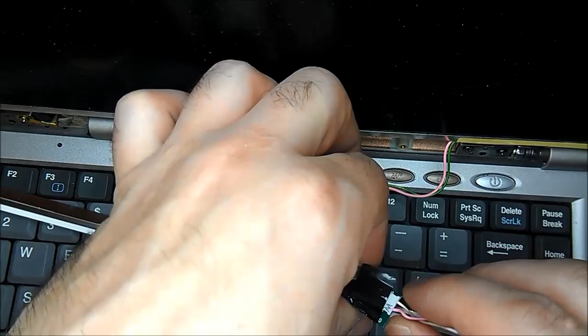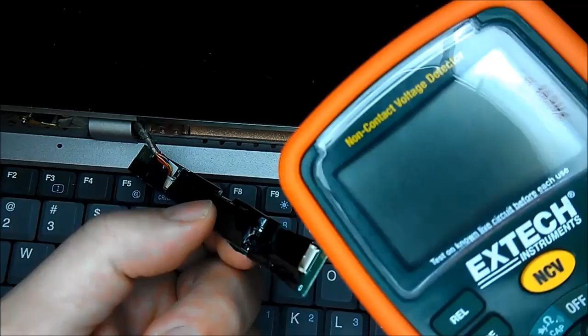Now, if you're tempted to check voltages, never check voltages on this side of the board. It doesn't matter what kind of meter you have. If it's one of these, they usually go up to 600 volts, or even one of these good ones, you'd need a very high-end meter over 1,000 volts. Usually the ones we carry go up to 600 volts. So you don't want to touch or probe that end to measure voltages, since it can be up to 900 something volts on that end, so stay away from it as much as possible.